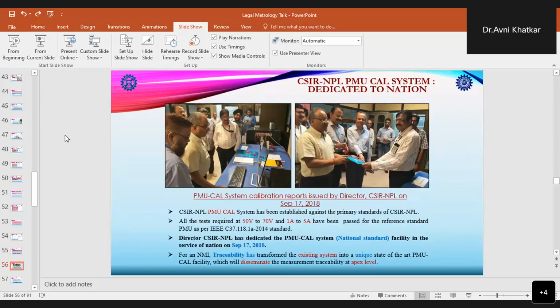And this CSIR NPL PMU calibration system was dedicated to the nation in 2018, and it is established against the primary standards of CSIR NPL. All the tests which are done by using the PMU calibration system are done from a voltage range of 50 volts to 220 volts, and at currents of 1 ampere up to 5 amperes, at different reporting rates as per the requirement of the test.